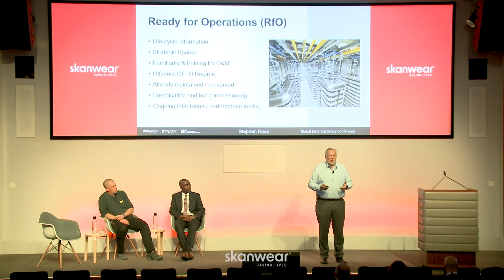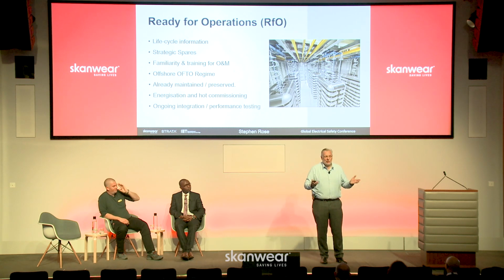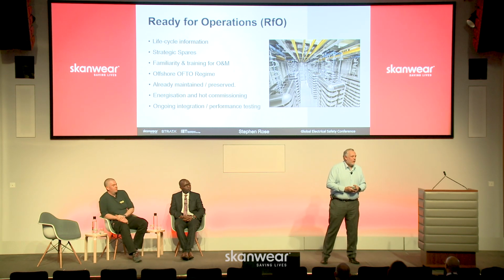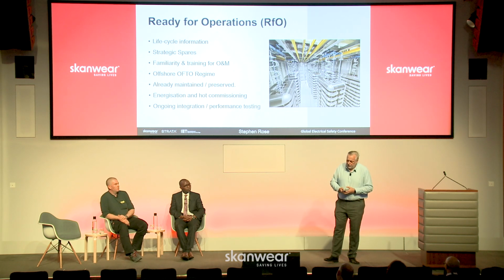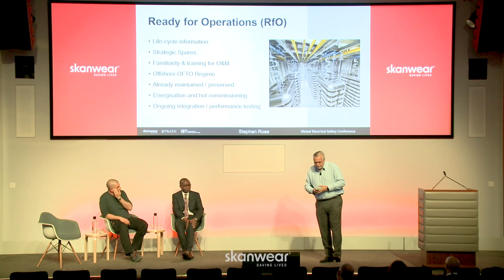We always try to make sure the O&M team are involved in commissioning. If we're good at our word, once it's on, it stays on, so they've got a one-shot opportunity to work on some of this equipment before it's energised. Once we're energised, we're not going to bring it off for any particular good reason. So having the operations team there alongside us to help with commissioning is really quite important.